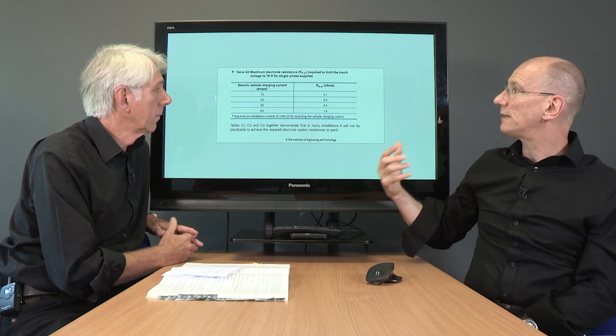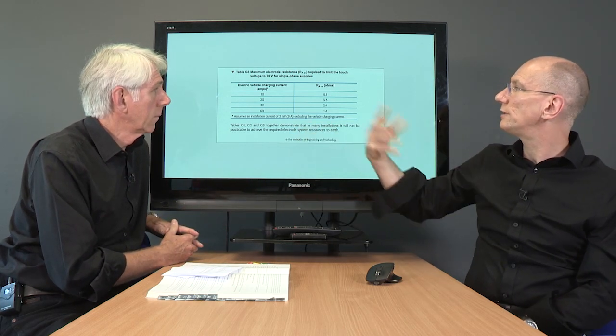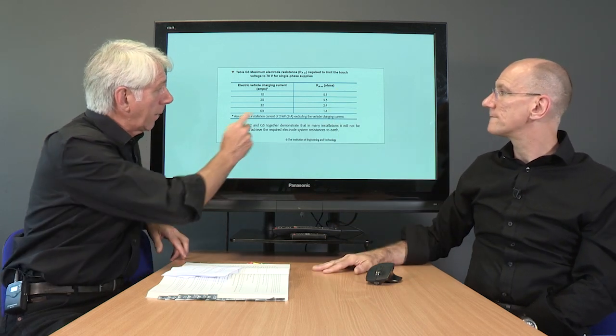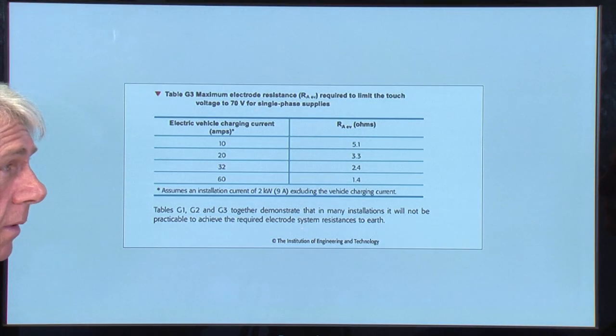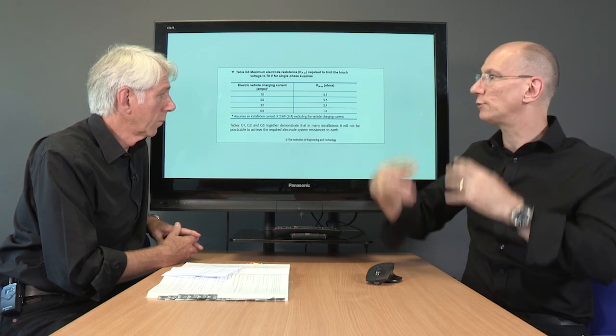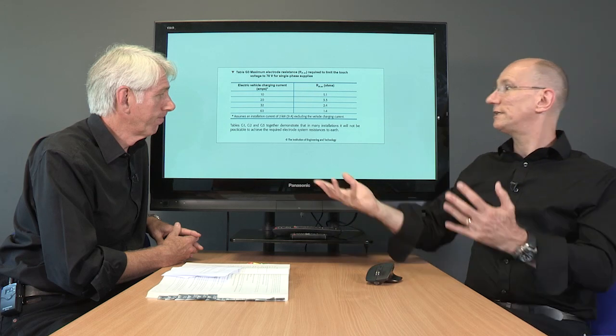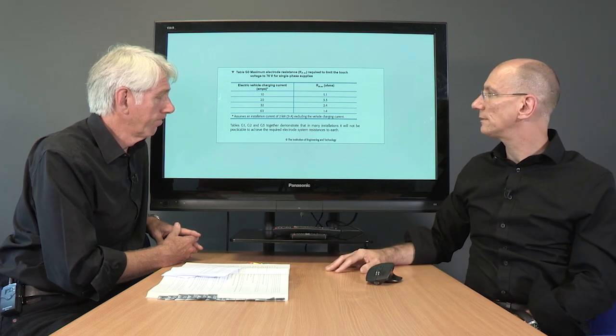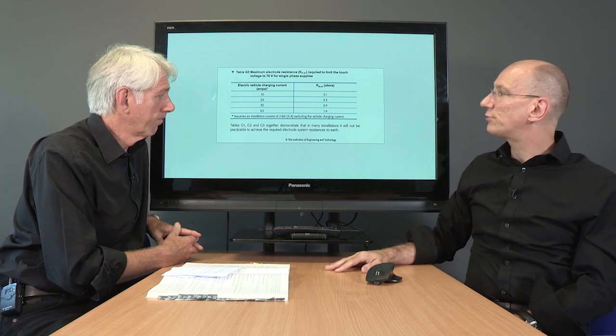That is. I mean, if you think about it, and if you've got other loads as well, you put it all into that, you would need a resistance on that electrode of 5 ohms. That's difficult to achieve, but when you go up to a fast charge current around 63 amps or 60 there, 1.4 ohms. And this is made reference to in another paragraph at the bottom of the page, which is with soil resistivity and the length of rods and the combination of 1 or 2 or 3 connected together. They demonstrate that in many installations, and you said earlier, could be most, and I think that probably is likely to be the case, it will not be practicable to achieve the required electrode resistance. So it's almost saying that that's out as well.